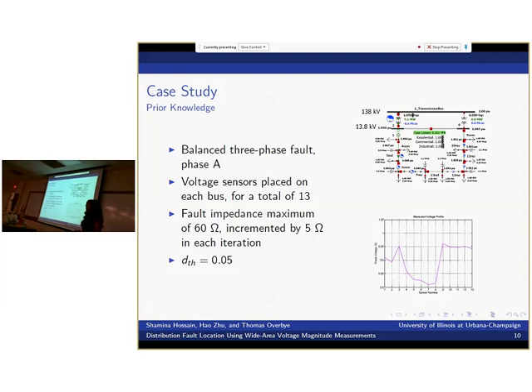So to demonstrate the use of our algorithm, we can go through a PowerWorld case study using the same feeder system presented before, the 13-bus system, with the measured voltage profile, where we're assuming the feeder system had at least one voltage sensor on each bus. Given these two, we're also given that a balanced three-phase fault in phase A has occurred, putting the system in a faulted condition. The fault impedance is deemed to be a maximum of 60 ohms, as determined by typical fault currents in distribution systems, and is incremented by 5 ohms in every iteration. And lastly, the threshold value is about 0.05.